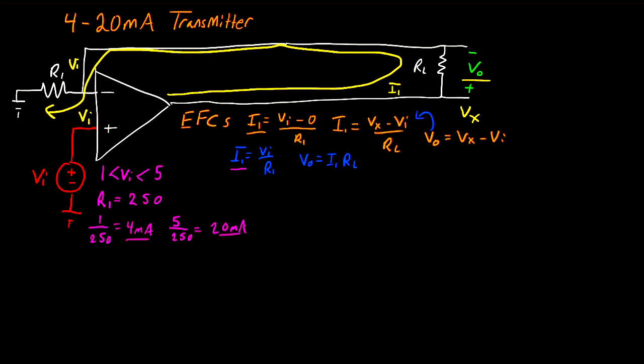So if we said that RL is equal to 250 as well, we could write that VO is equal to 250 multiplied by I. Now if I is equal to 4 milliamps, VO is going to be equal to 1 volt. And if I is equal to 20 milliamps, VO is equal to 5 volts. So in this way, we can take a voltage, turn it into a current, and then measure a voltage at the output in response to that that's the same as our input voltage.